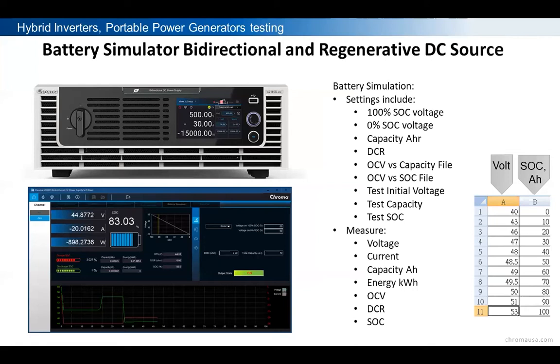Measurements on this unit are very good. It gives you voltage, current, ampere hours, kilowatt hours for energy, open circuit voltage, DC resistance, and state of charge. All of these can be measured, captured from the unit into the software, and shared into a data file. Creating those curves is very simple to do, you can do it from an Excel file that includes voltage based on state of charge, with data points usually collected from information your battery manufacturer provides. So we can truly simulate that actual battery if needed.